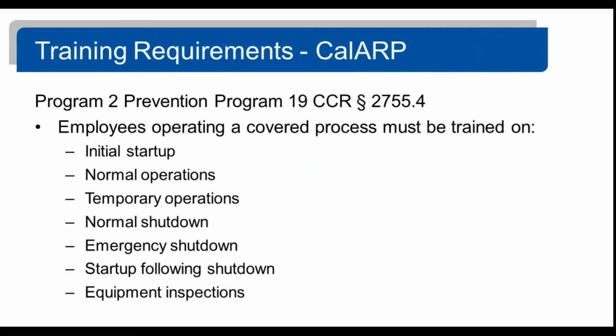dependent on which program you may be subject to. So for Program 2 facilities, training requirements are spelled out in state regulations, Title 19, California Code of Regulations, Part 2755.4. And employees that operate a covered process must be trained on the following elements: initial startup, normal operations, temporary operations, normal shutdown, emergency shutdown, startup following shutdown, and then equipment inspections.